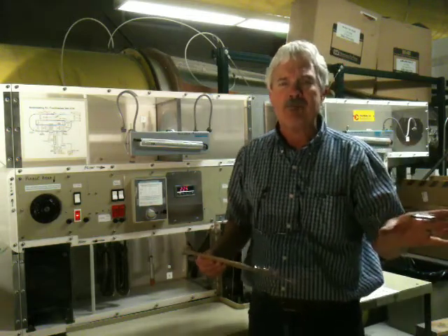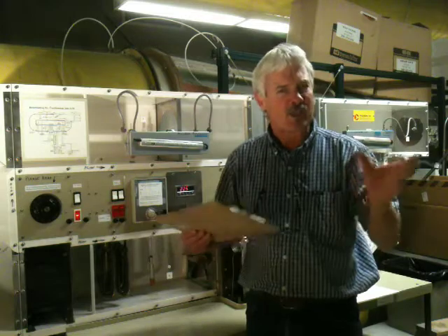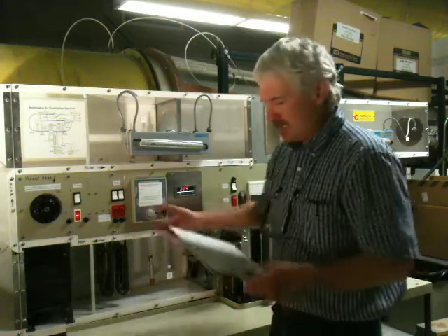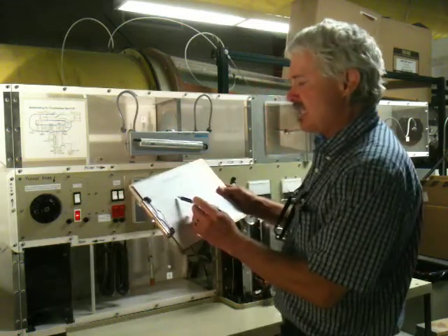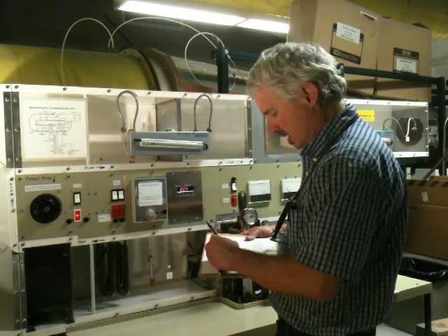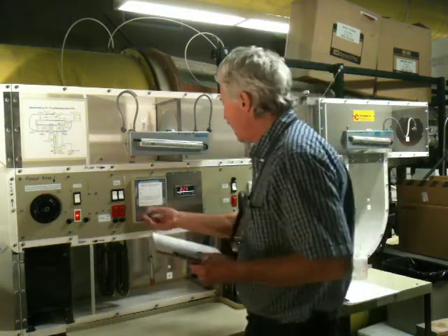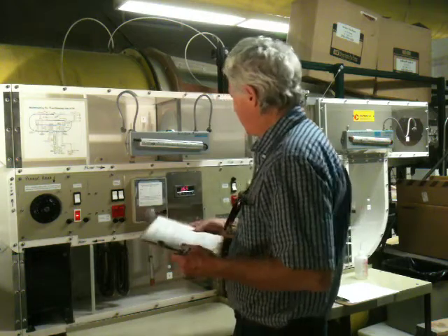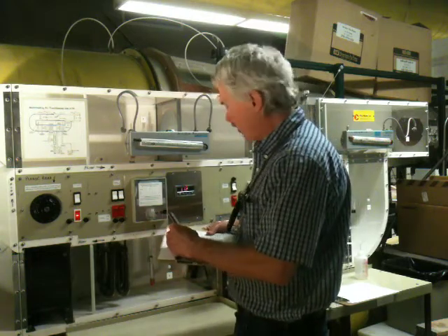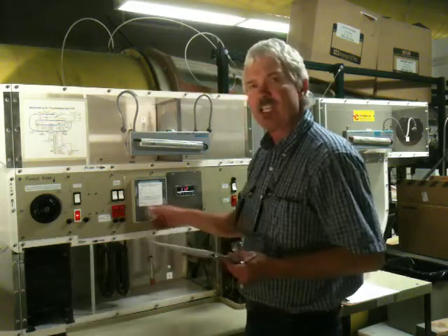Then for the other tests, I will probably show you the relevant measurements. We'll see how these unfold, but I don't want to take up a lot of your time with this. So section A, test station A, dry bulb, 22.5. A wet, 11.2, 11.3 degrees centigrade.